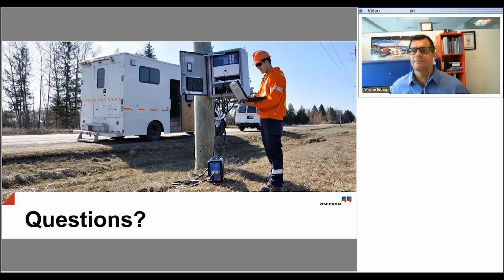The question is, when testing a scheme in the field using the cloud application, does the latency of the cloud affect the testing of the scheme? It should not, because all we're using the cloud to do is to send all of the test requirements to all of the individual test sets, and then based on the GPS coordination, they can start all of the tests at the same time. Once all the tests are started, it injects, it gets the feedback from the system, or each individual recloser holds the data and then sends the data back through the cloud. So that shouldn't add any additional latency to any kind of scheme operation, only maybe to the duration of the test.